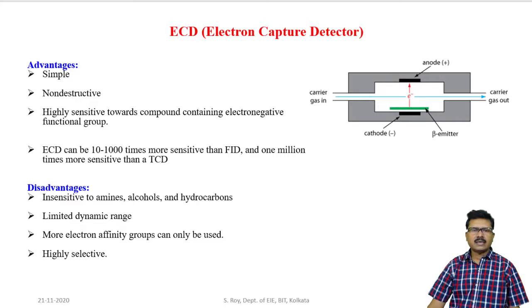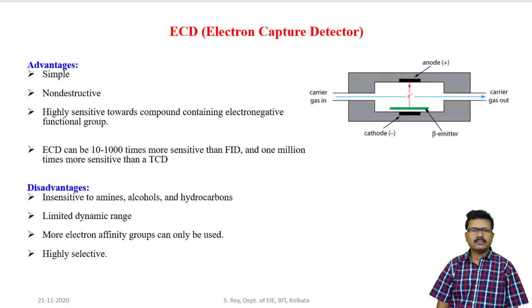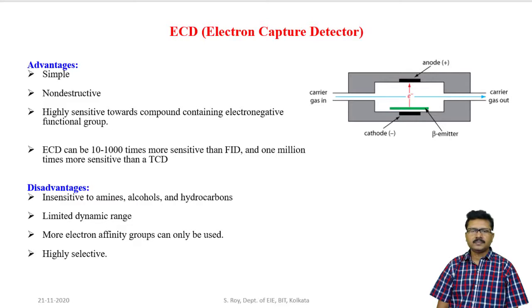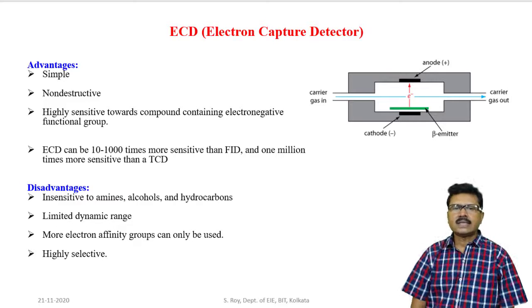Advantages of electron capture detector: it is simple in construction and, most importantly, it is non-destructive — it does not have any effect on the sample, so we can collect and reuse the sample. It is highly sensitive for electronegative compounds and can be 10 to 1000 times more sensitive than flame ionization detector, and 1 million times more sensitive than thermal conductivity detector. Disadvantages: it is insensitive to amines, alcohols, and hydrocarbons. It has a very limited dynamic range and is limited only to samples with high electron affinity, meaning it is highly selective.